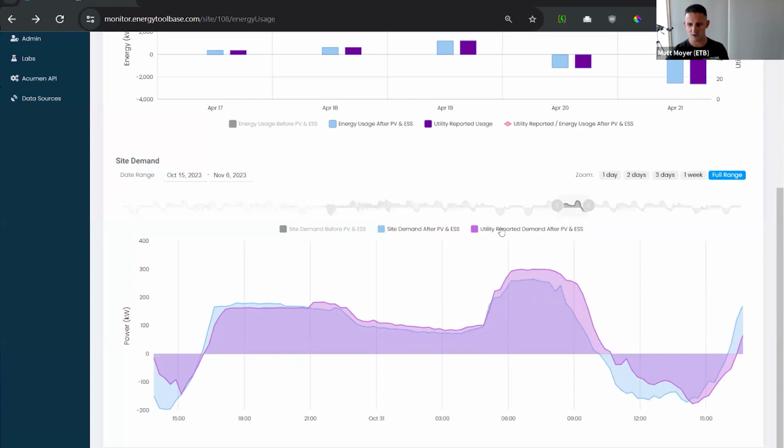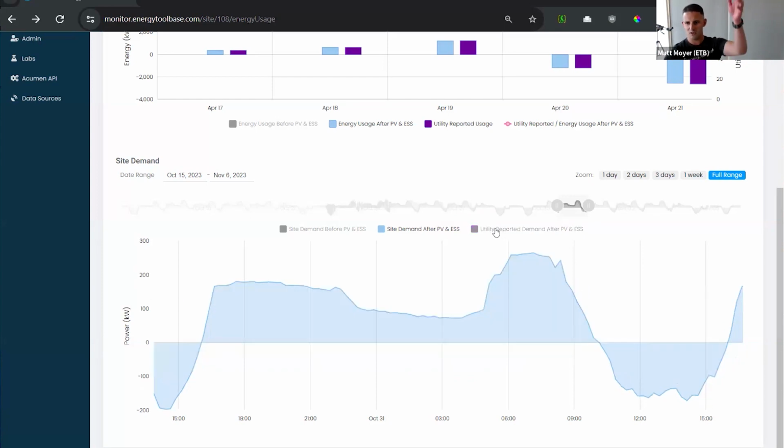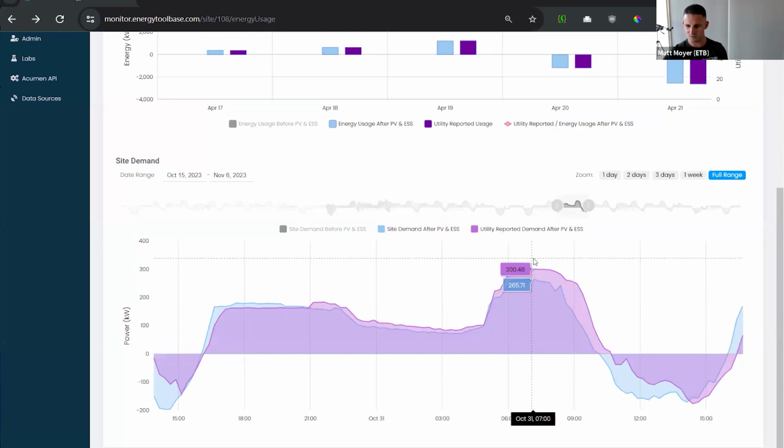If you look at our data, that big demand charge that makes up 50% of their bill was 265 kilowatts at their biggest spike, and they were getting billed for 300. At $20 a kilowatt, it actually made a sizable difference on their bill, where it was manufacturing new peaks that didn't actually exist. And that's what actually triggered the bills being so far off. Wow, quite interesting.